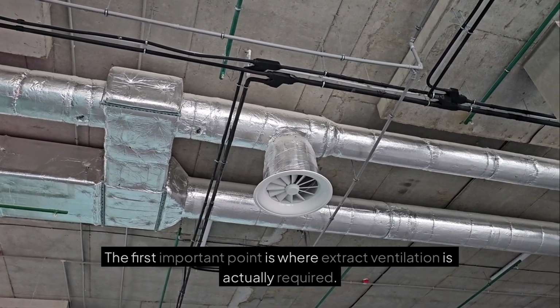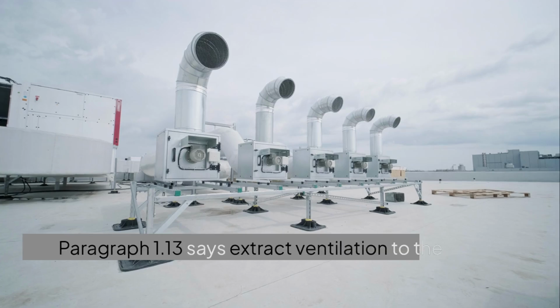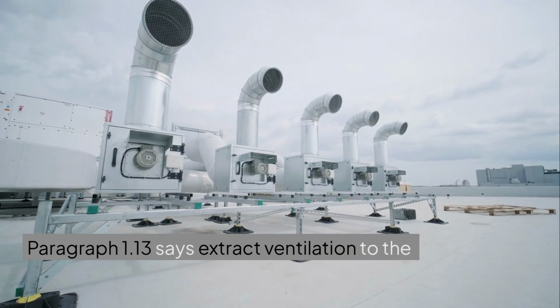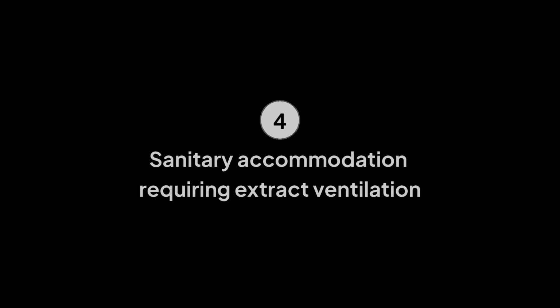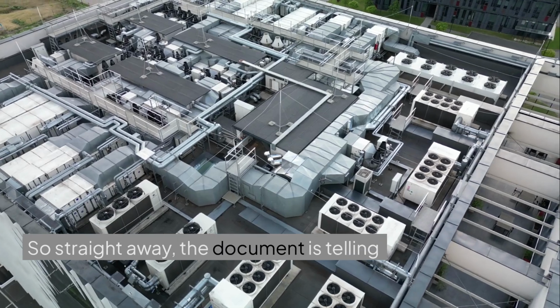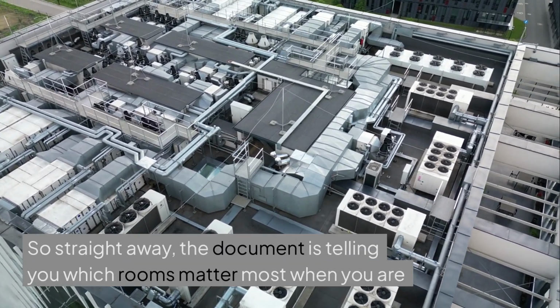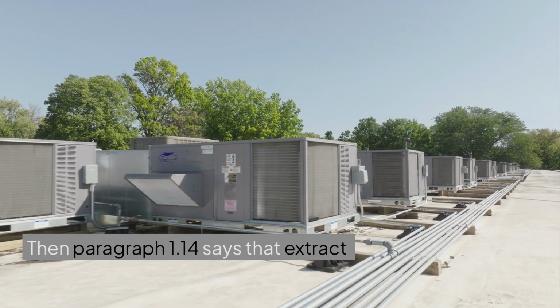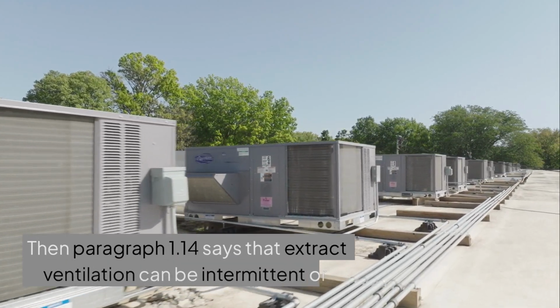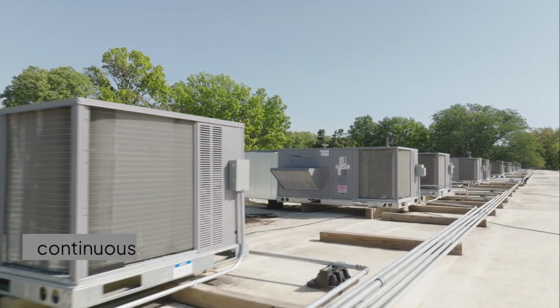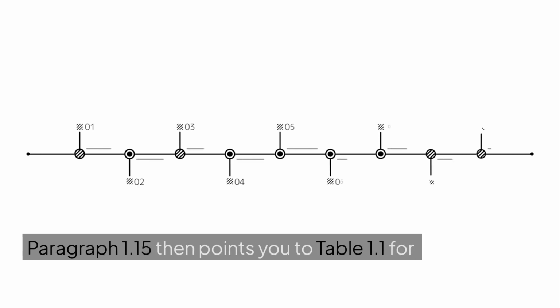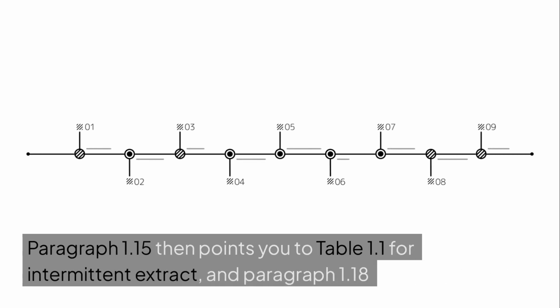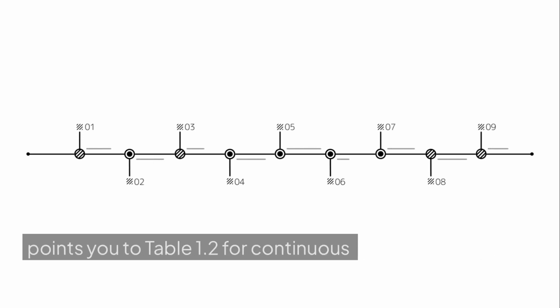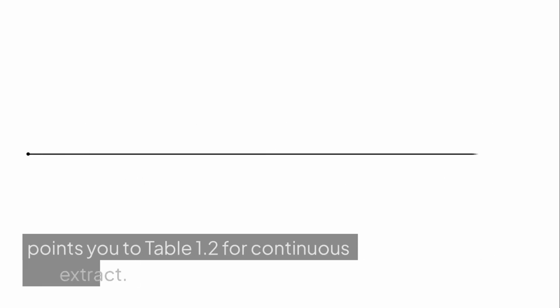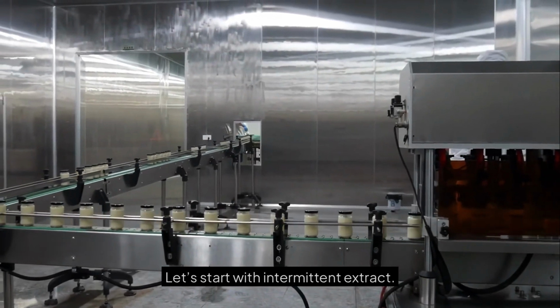The first important point is where extract ventilation is actually required. Paragraph 1.13 says, extract ventilation to the outside should be provided in kitchens, utility rooms, bathrooms, and sanitary accommodation. So straight away, the document is telling you which rooms matter most when you are thinking about extract design. Then paragraph 1.14 says that extract ventilation can be intermittent or continuous. Paragraph 1.15 then points you to table 1.1 for intermittent extract, and paragraph 1.18 points you to table 1.2 for continuous extract. Let's start with intermittent extract.